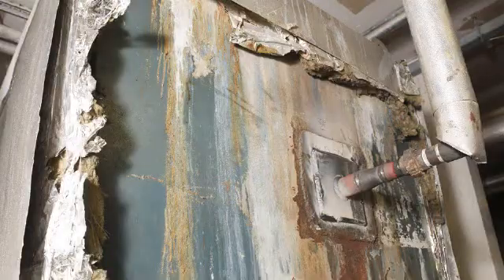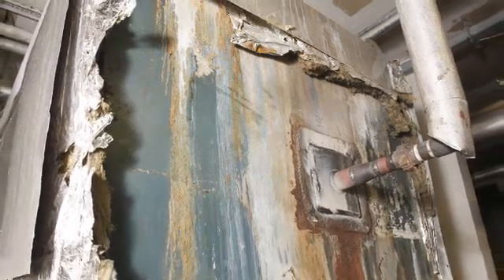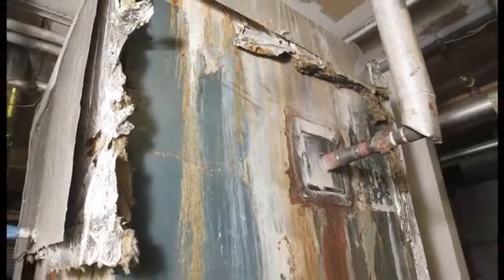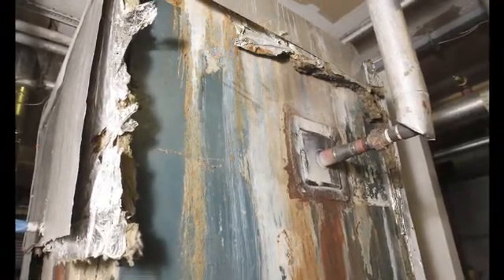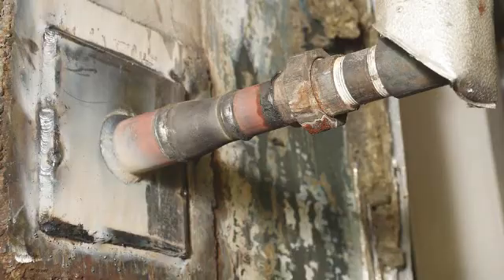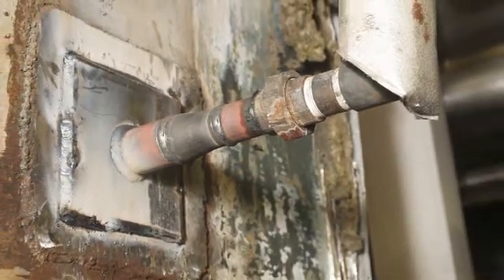The hot well tank stores returned condensate from the site. This is hot water that will be returned to the boiler system for steam generation. The water in the hot well should be as hot as possible, typically over 80 degrees centigrade. This picture shows that the side wall of the hot well has not been insulated after repairs were undertaken to stop a leak.